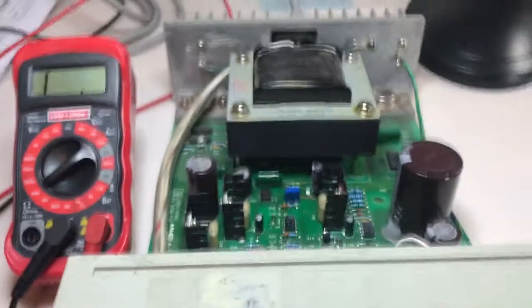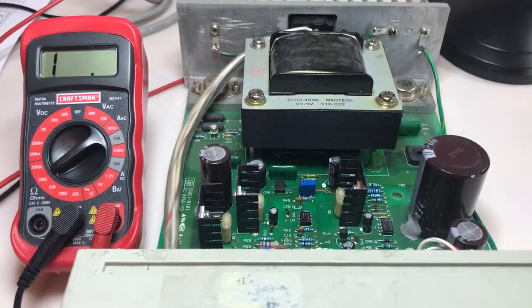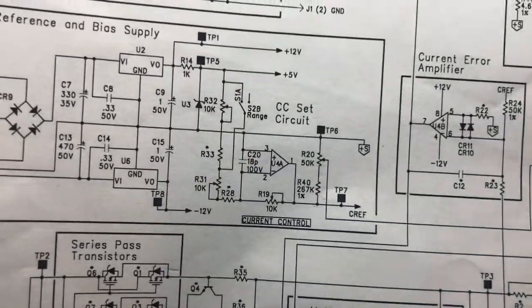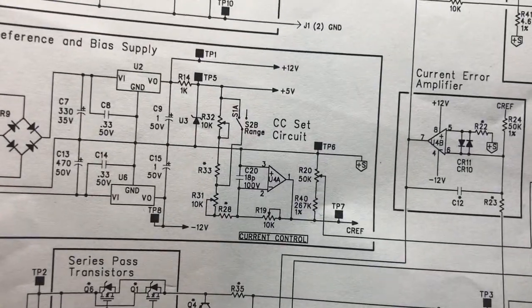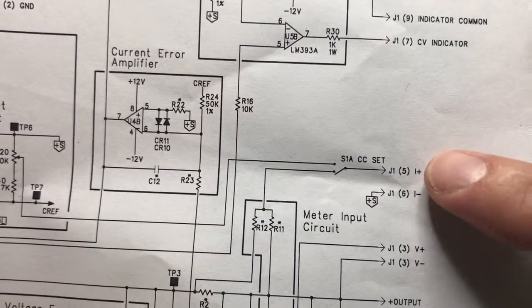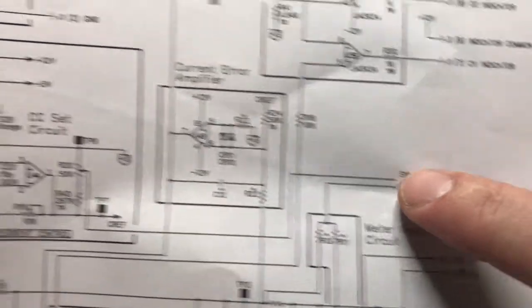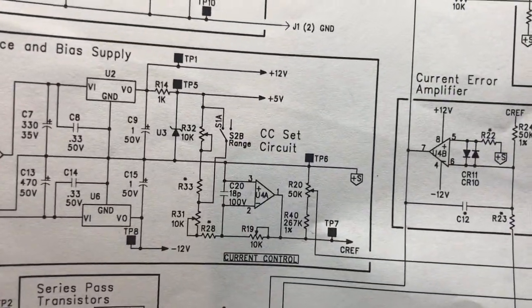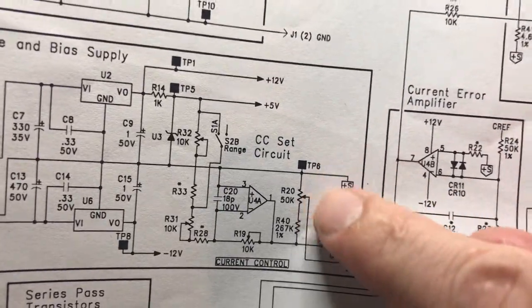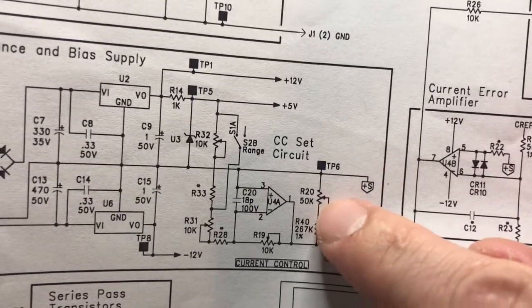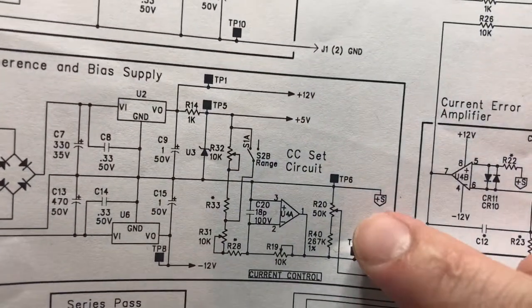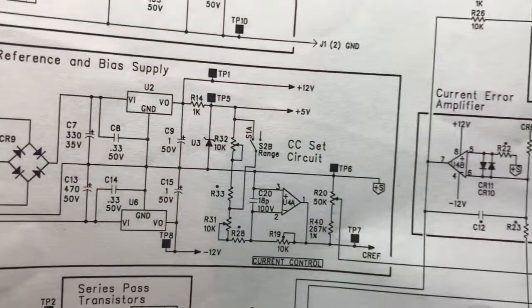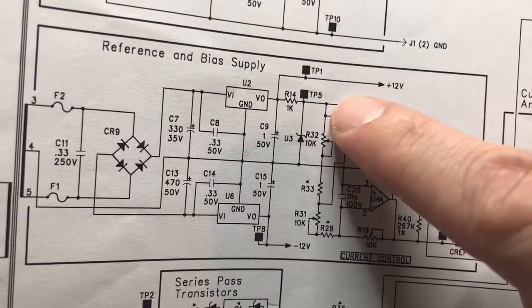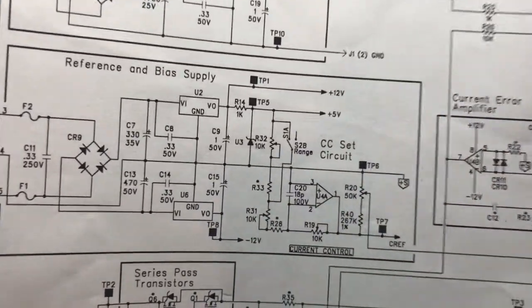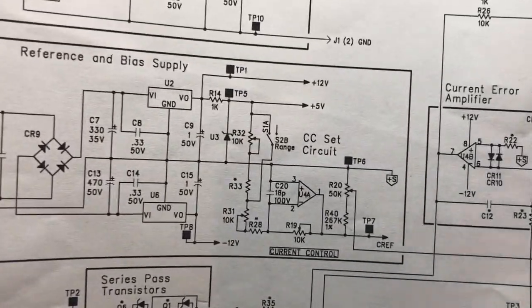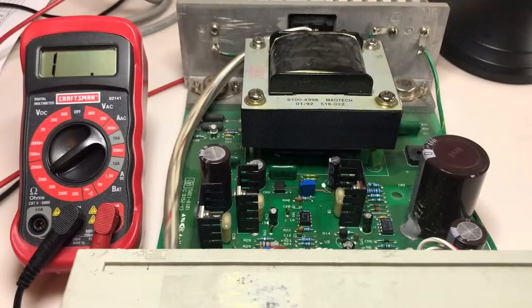So if we go back to the schematic again, where I'm getting voltage is right here. In between R40 and R20, I'm reading voltage because, again, if we look over here, our constant current set is reading between positive S and the center tap of R20. So that's just really test point 6 to the center tap of R20, which means there has to be a voltage at the base down here of R20. So when I measure voltage here, I get a voltage. When I measure voltage on the other side of R40, I get no voltage. How is that possible? Our 5-volt rail is up here. We're coming down through all these resistors, and we should be dropping all the way down to the positive S at test point 6. But yet I'm getting a voltage injection in between R40 and R20. Didn't really seem possible.